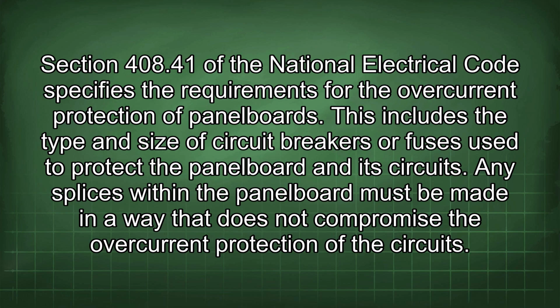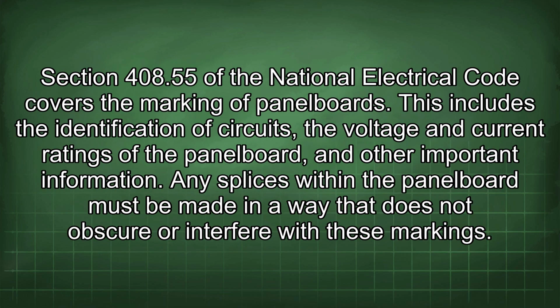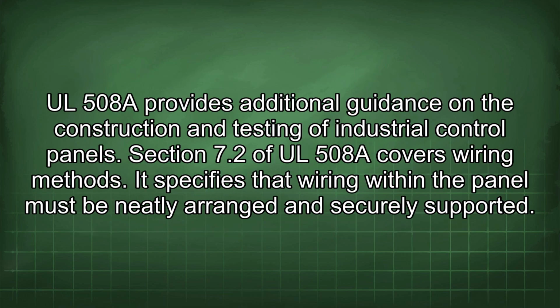Any splices within the panel board must be made in a way that does not compromise the overcurrent protection of the circuits. Section 408.55 of the National Electrical Code covers the marking of panel boards. This includes the identification of circuits, the voltage and current ratings of the panel board, and other important information. Any splices within the panel board must be made in a way that does not obscure or interfere with these markings.